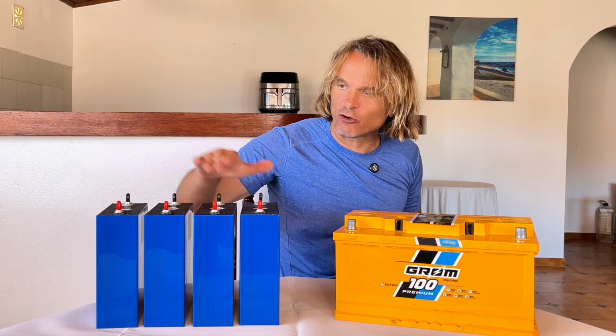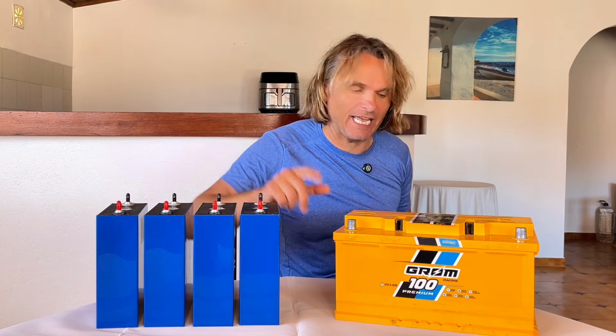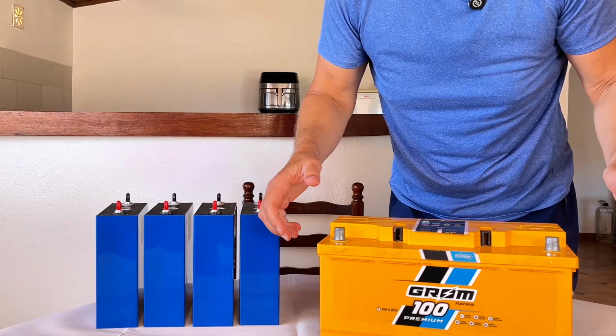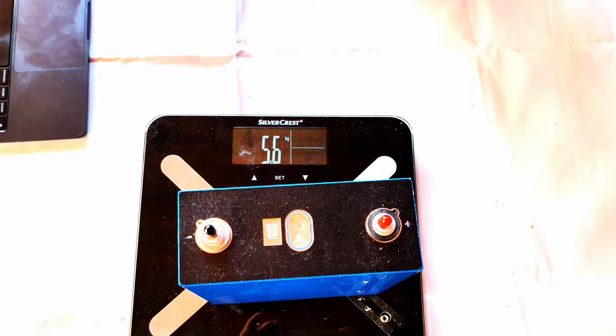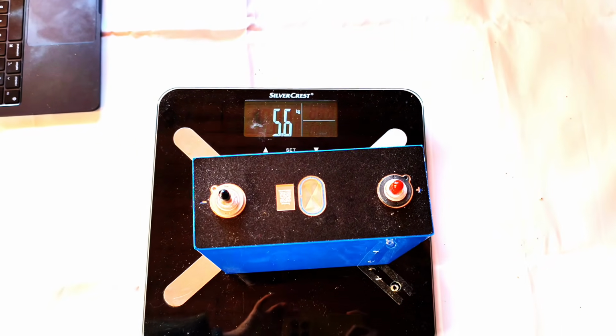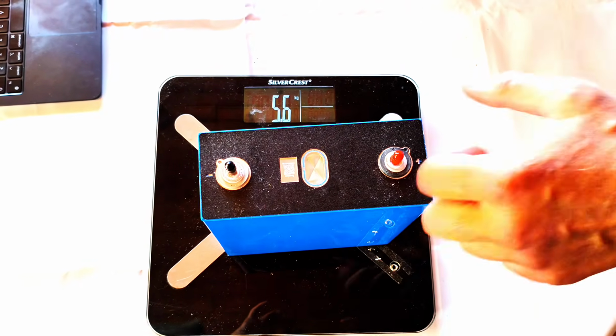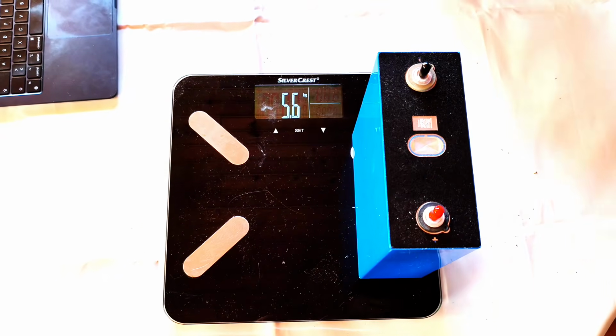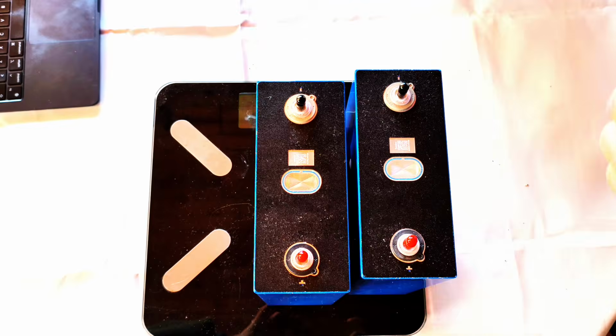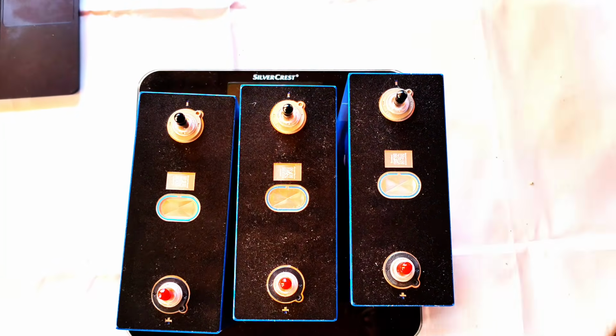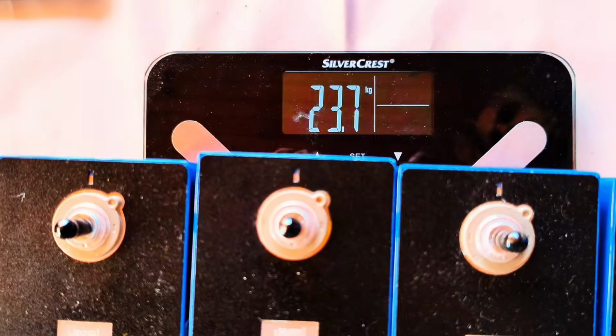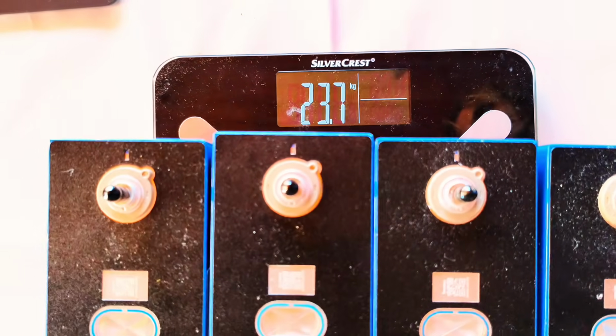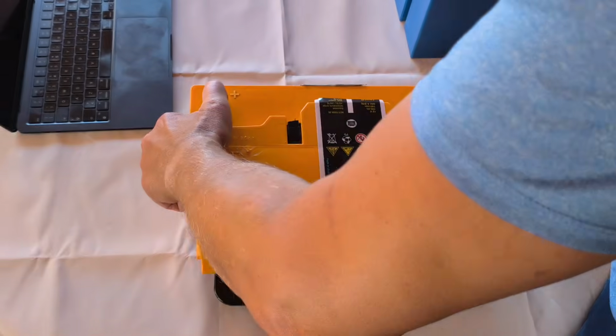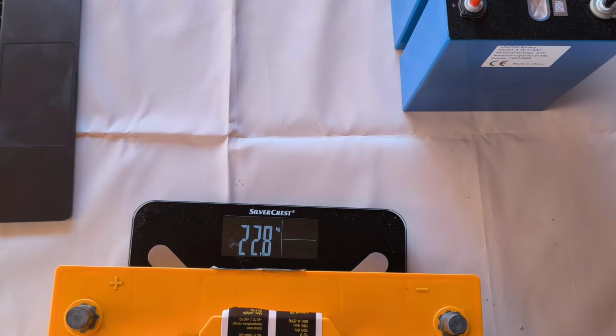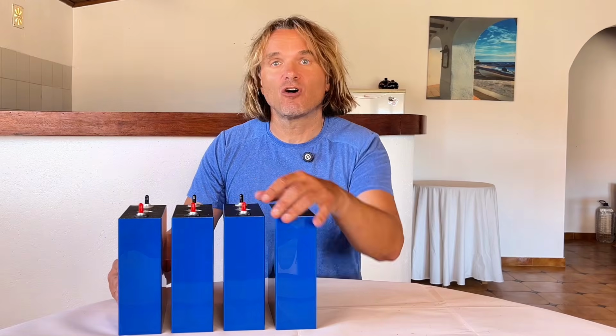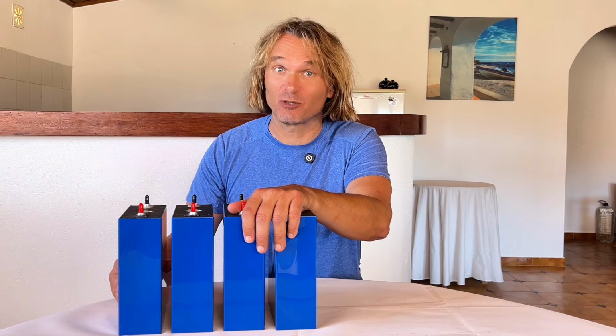Now we have 4 times more energy. Every kilowatt hour in LFP batteries is 5.6 kilograms, and together 4 of them is 23.7, which is almost the same as 1 kilowatt hour in a lead acid battery. So, 4 times the storage and almost the same weight.